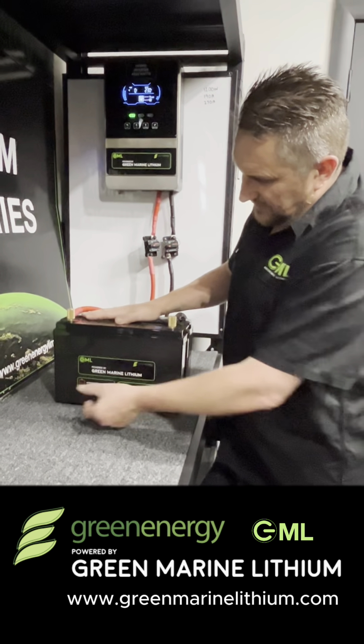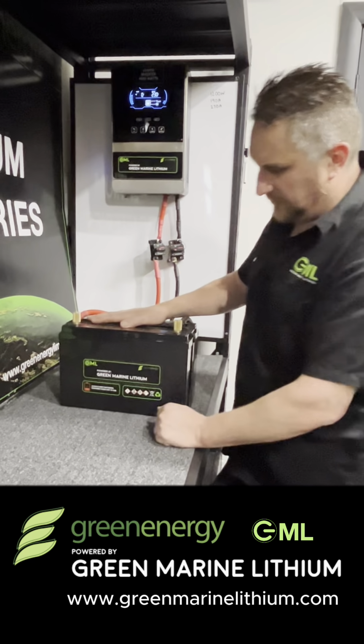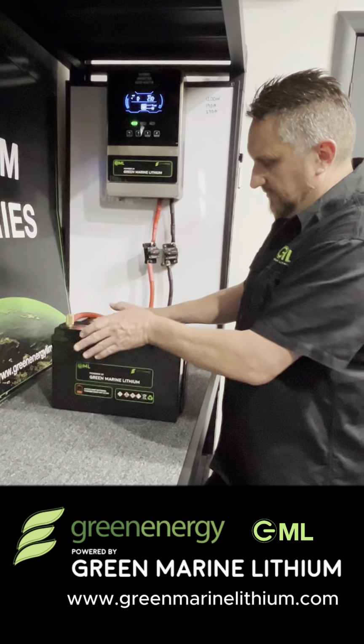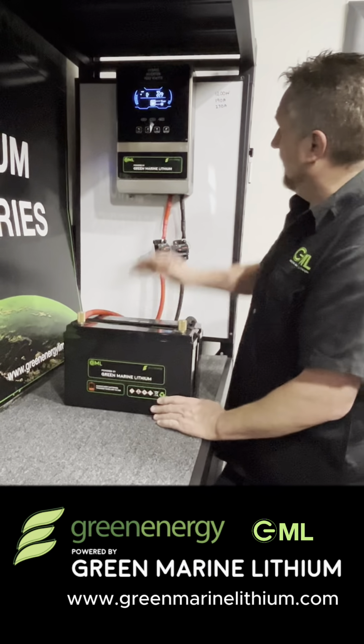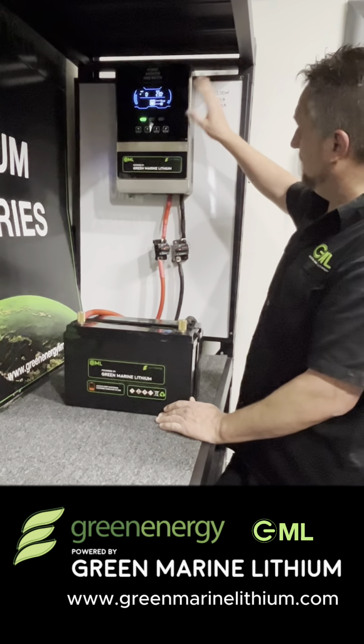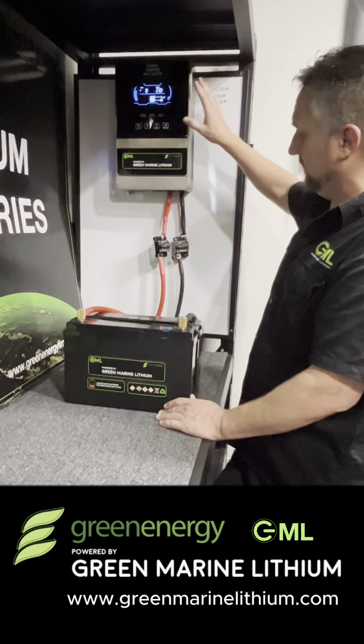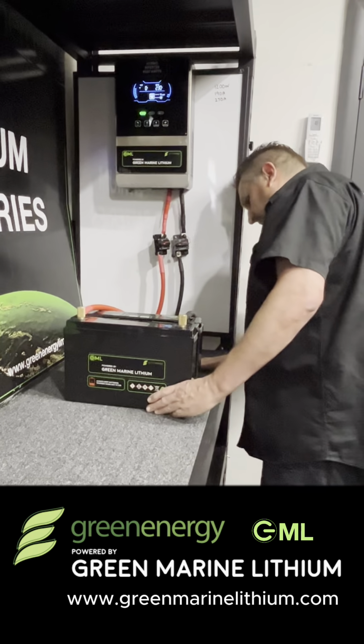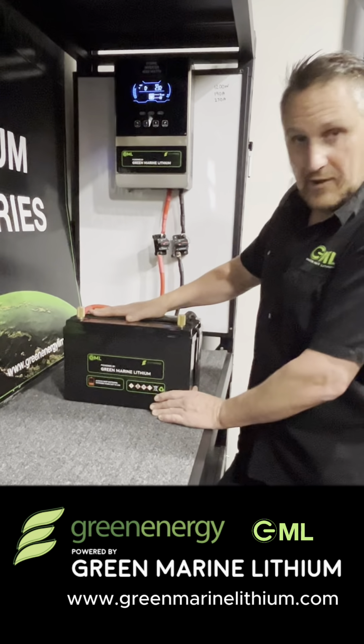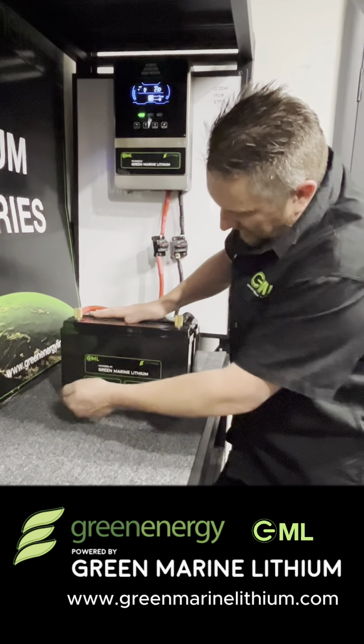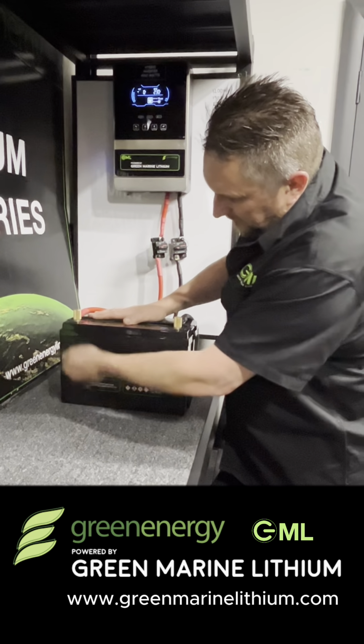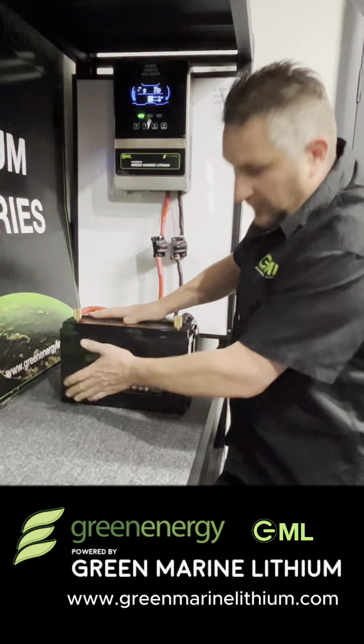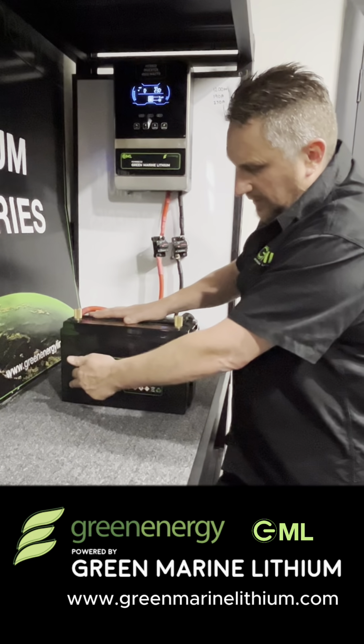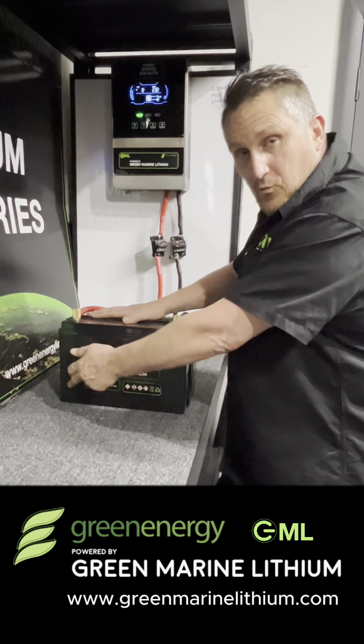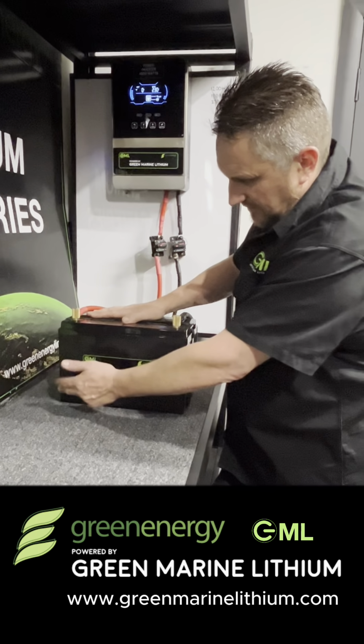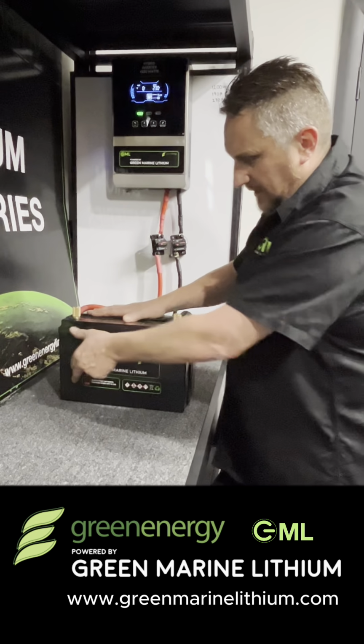What's important is to know the size of the cell inside the battery, the output of the BMS, and matching it to the input requirement for the inverter. This battery here is a 24 volt 50 amp hour battery, a green marine battery, and the cell inside is a 50 amp cell. That means the cell has a maximum discharge of 1C, which is its capacity, meaning it can produce 50 amps.